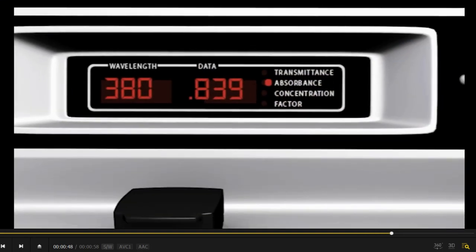And then, after that, this is going to be recorded with the help of detector. Now, the function of detector is to convert the light radiation energy coming from the sample cell into electric signal. So, common photodetectors are photocell, photomultiplier tube. Inside the detector is amplifier as well.